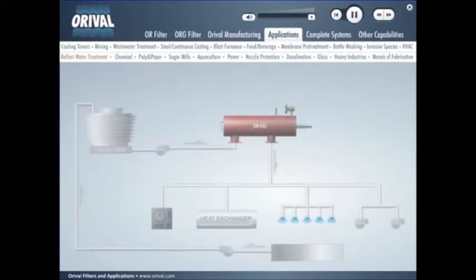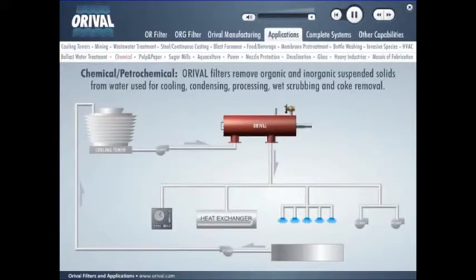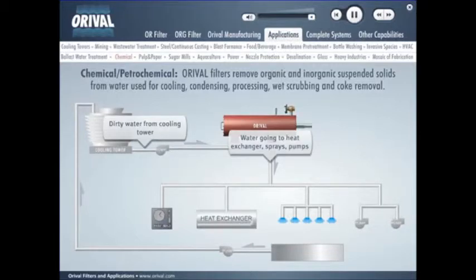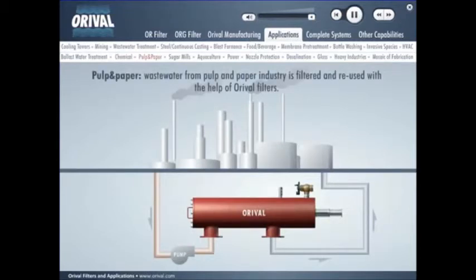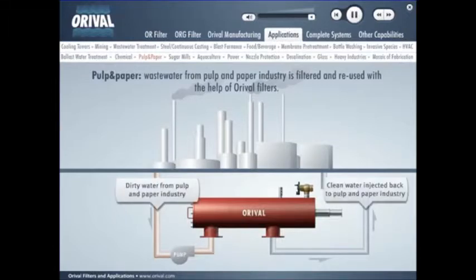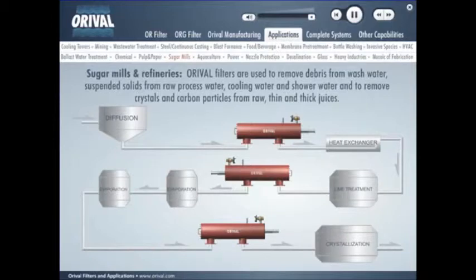Orival filters remove organic and inorganic suspended solids from water used for cooling, condensing, processing, wet scrubbing, and coke removal. Dirty water from the cooling tower is filtered and reused in heat exchangers, sprays, and pumps. Wastewater from the pulp and paper industry is filtered and reused with the help of Orival filters. In sugar mills and refineries, Orival filters are used to remove debris from wash water, raw process water, cooling water, and shower water, and to remove crystals and carbon particles from raw, thin, and thick juices. Filtered water can be reused in heat exchangers and evaporation stages.